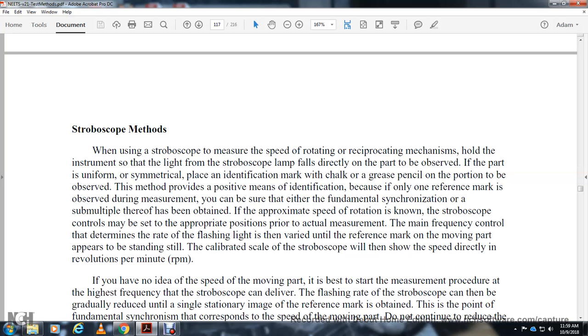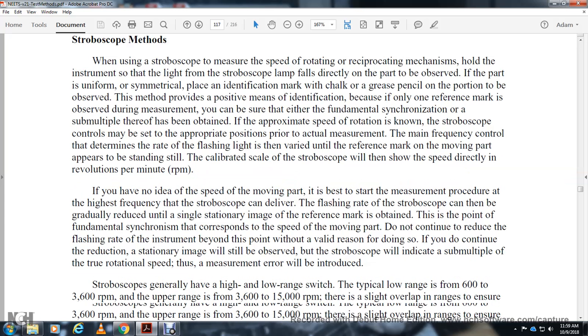If the approximate speed of rotation is known, the stroboscope may be set to the appropriate position prior to the actual measurement. The main frequency control determines the rate of the flashing light. The reference mark on the moving part will appear to stand still, and the calibrated scale of the stroboscope will show the speed directly in revolutions per minute.